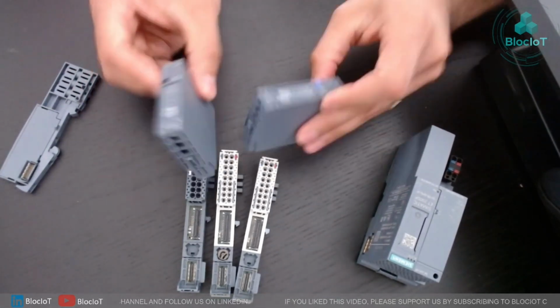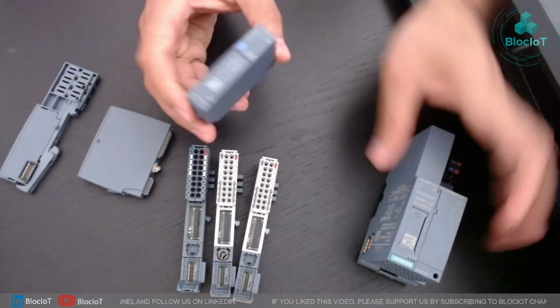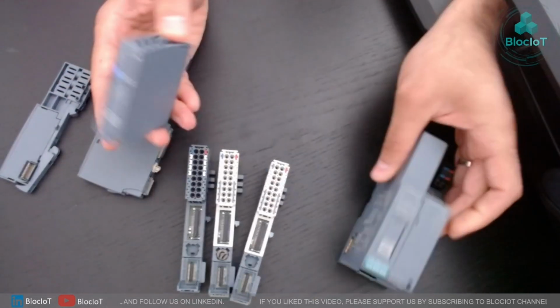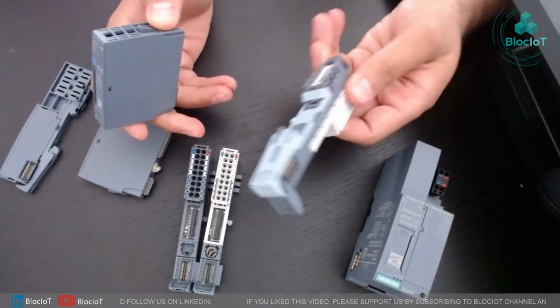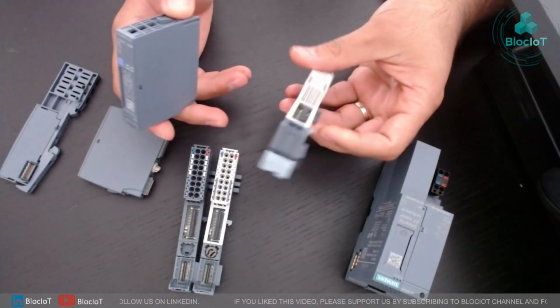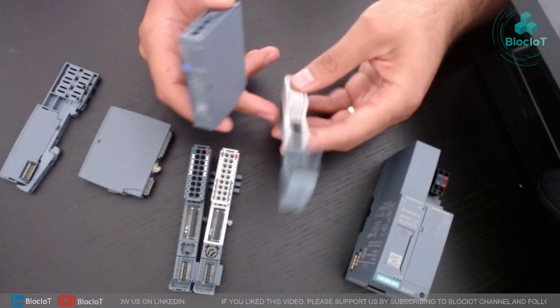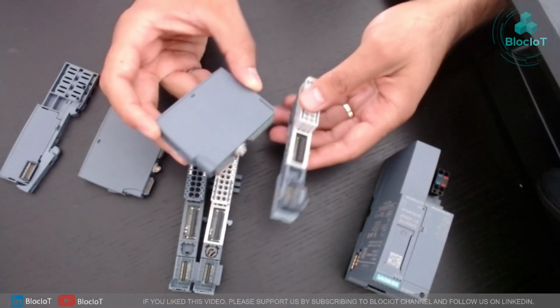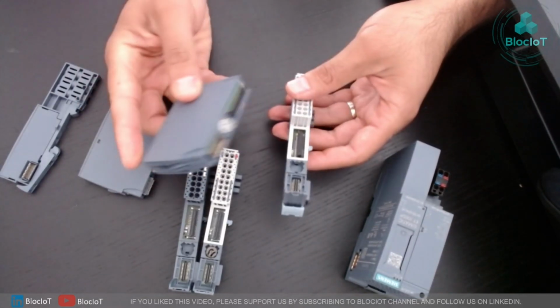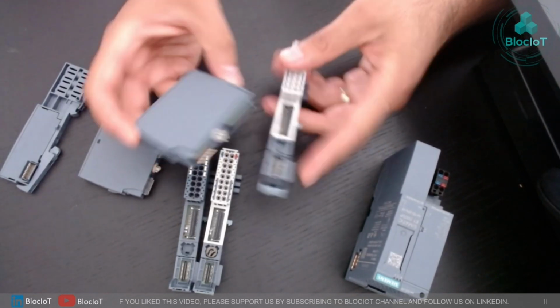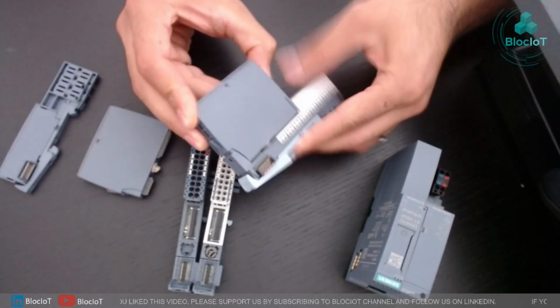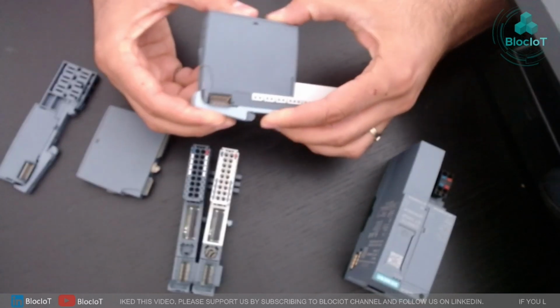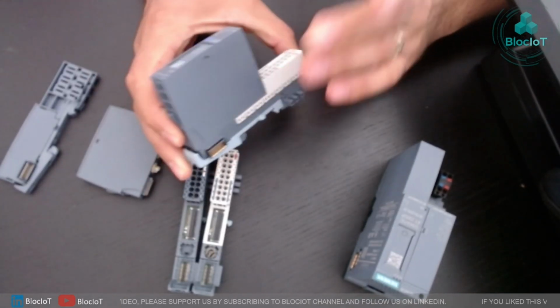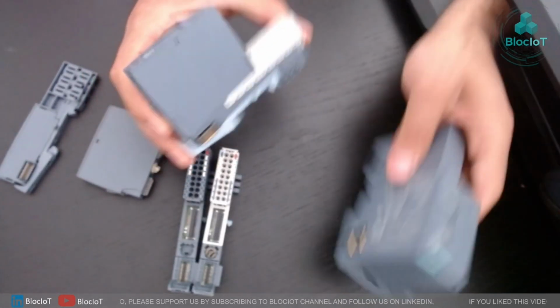As you can see, the I/O module looks like this, and you cannot just attach them directly. That's why we have something called a base module, and you can use it to attach your I/O card. As you can see, there are two connectors on these base modules. It just snaps together, and this package, which is a module and a base module, can be connected to the interface module.